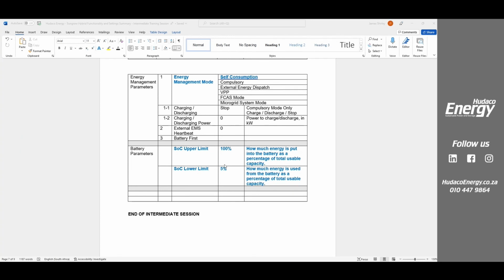Remember, this is different to your reserve state of charge. This upper limit and lower limit are the limits to which you're allowing the system to use your batteries. The reserve state of charge is a level to which you set your self-consumption mode and how much of that energy within this range you are keeping for backup only. In other words, once grid falls away. Okay, so those are 2 different modes.